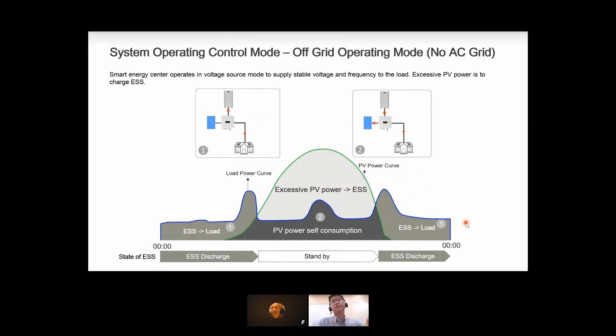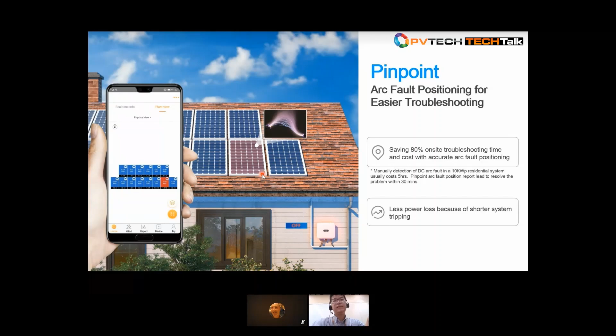So how can we do the O&M? Another great feature is pinpoint arc fault positioning. We know that with conventional approaches, because some of the arcing faults hide below the modules, we do not know specifically where they are located. But with Huawei Smart PV optimizers, we can now achieve module-level fault location. So it can save installers a lot of time, because they don't need to go on site and do string inspection, which takes a very long time. Now they can locate the problem accurately and do the replacement quickly.